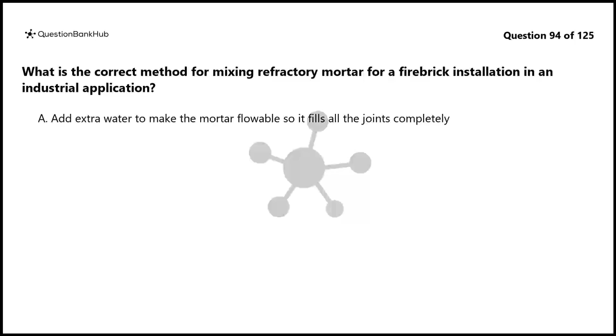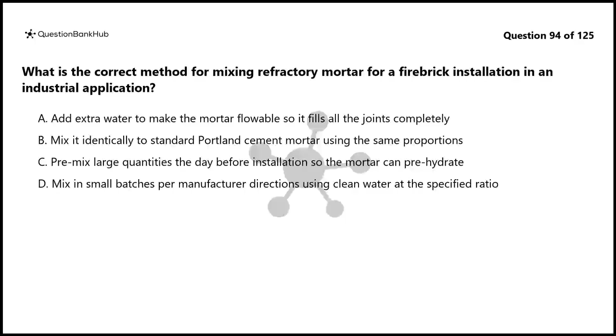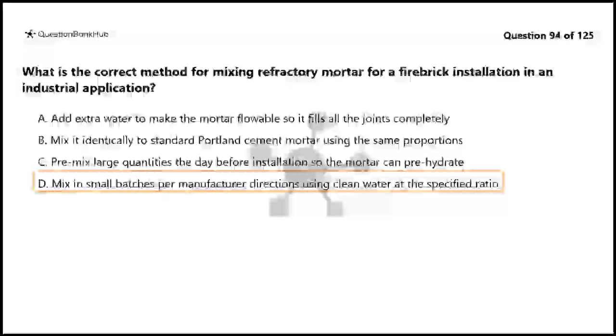Question 94. What is the correct method for mixing refractory mortar for a firebrick installation in an industrial application? Refractory mortar must be mixed in small batches following the manufacturer's specific directions, using clean water at the exact ratio specified. The working time of refractory mortar varies by type and can be quite short.